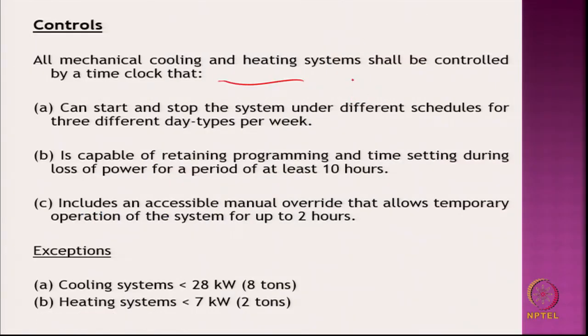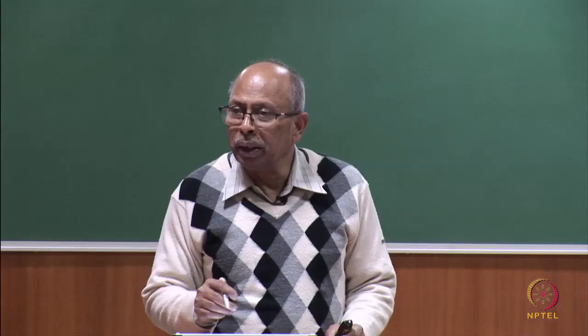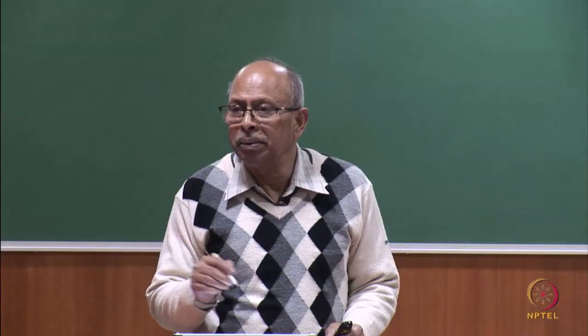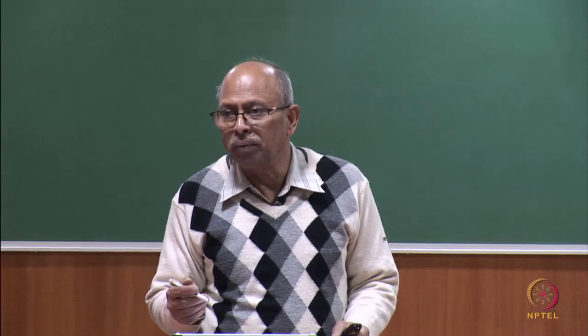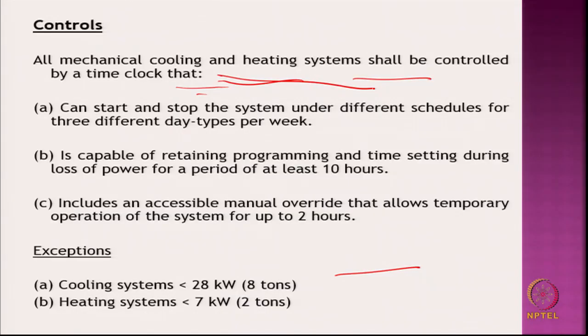Controls: all mechanical and heating systems shall be controlled. I think I was mentioning this in the last class, there might be a 2-point off-on control minimum. That means it is put on at 8 a.m. If the office is starting at 9 a.m., it is put on at around 8 or 8:30 a.m. and then remains on for some hours and then is put off. So, there is a control system that has to be there, which can start and stop the system under different schedules, and as I was mentioning in the last class, at least 3 different schedules could be there.